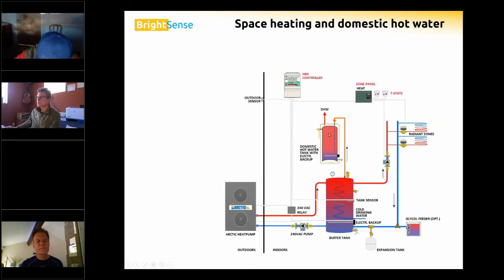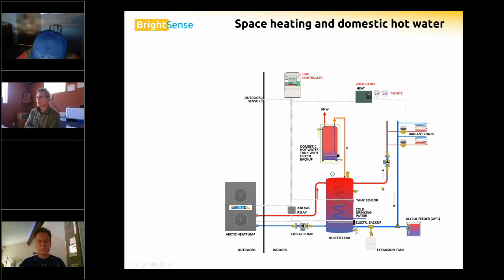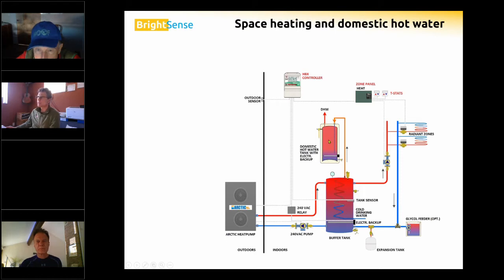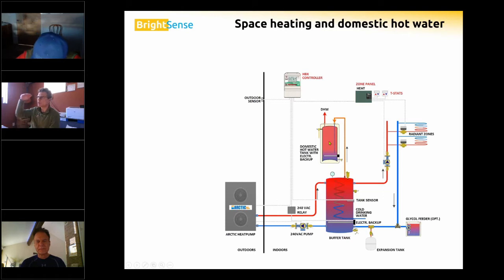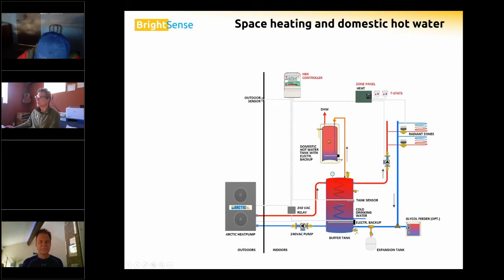Here's a space heating and domestic hot water system. In the buffer tank there's a coil that preheats domestic hot water, which then flows into the actual domestic hot water tank. For those requiring 140-degree water temperature, that tank boosts temperature a few more degrees. If someone has a large soaking bathtub, it adds the required capacity.